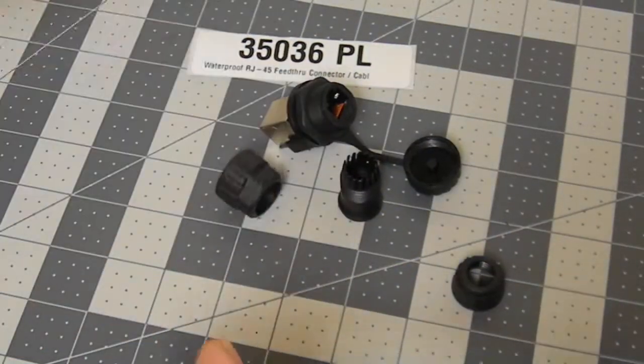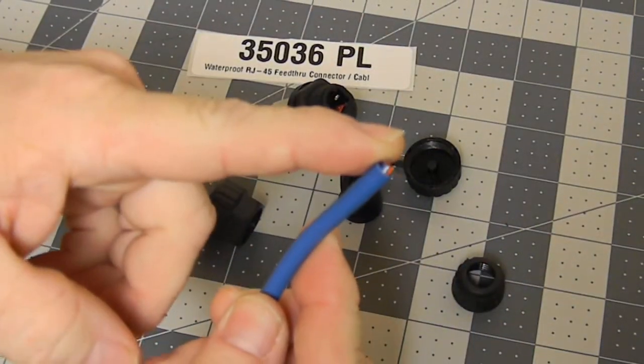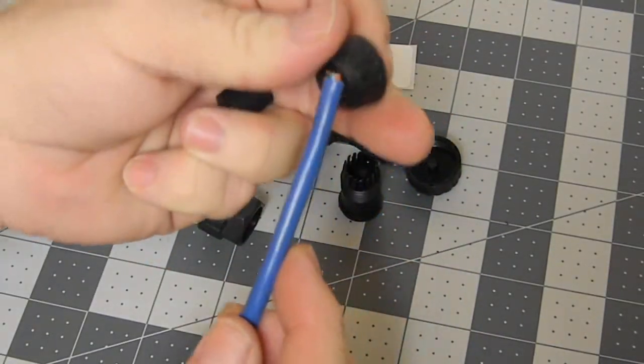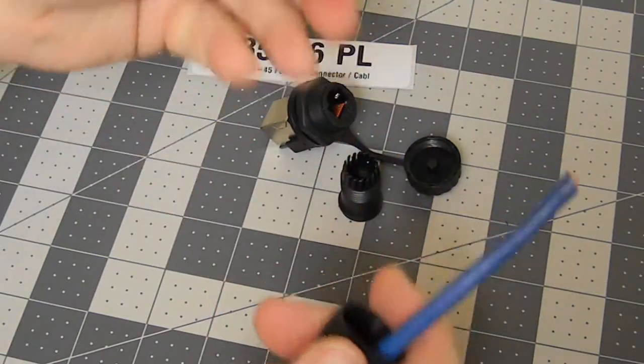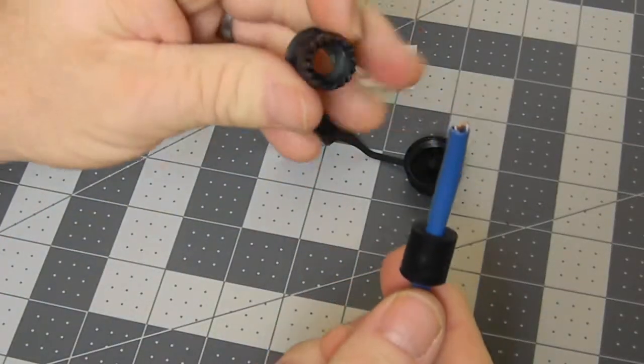Now to get it to the water rating, the IP67, you must start off with a plain cable with no connector on it. It must be applied later. That's the only way you could get the sealing grommet to slide over the cable.